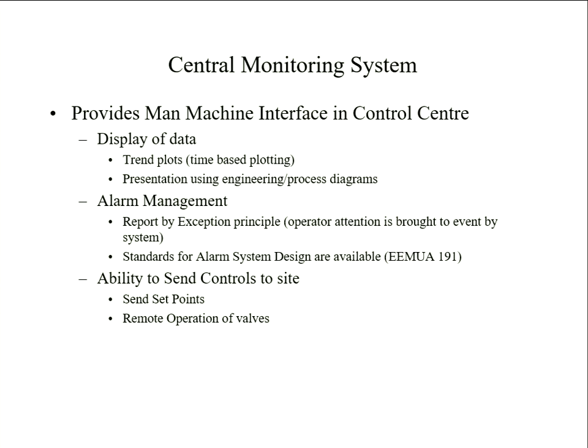So the national transmission system, all the pressures and flows and valves and compressor data is fed into an online system along with future nominations, and is continuously generating a forward prediction of what's going to happen on the network over the next 24 hours. Of course, somebody then changes their nomination and it makes it wrong, but it'll do things like state reconstruction. Some of the leakage detection systems rely on that sort of thing. So you're starting to connect to bigger, non-operational systems, so business systems, classically billing, but it might be nomination notification systems.